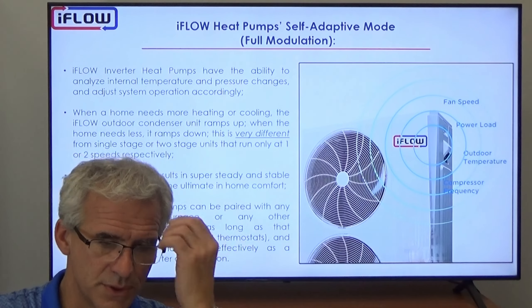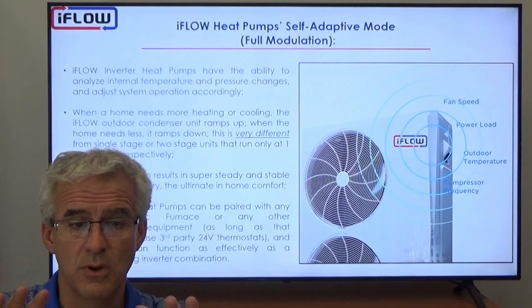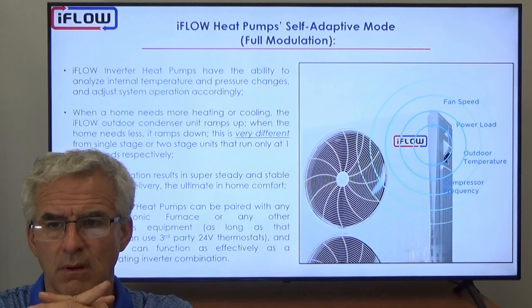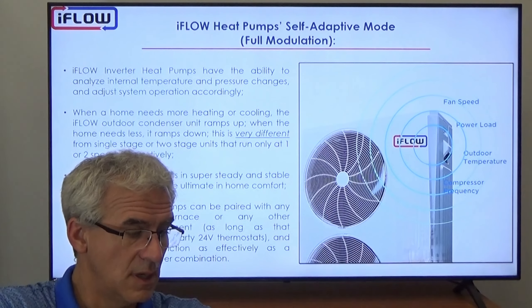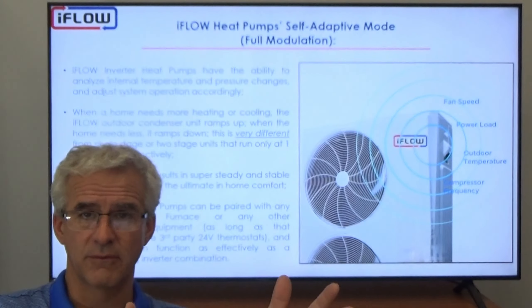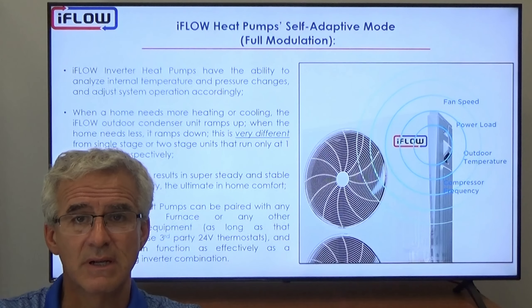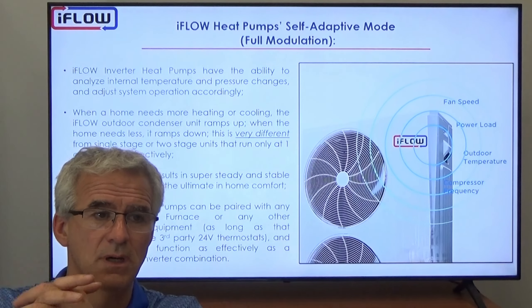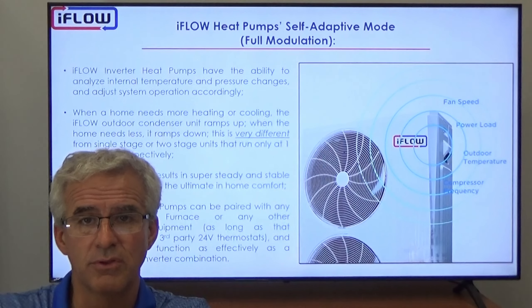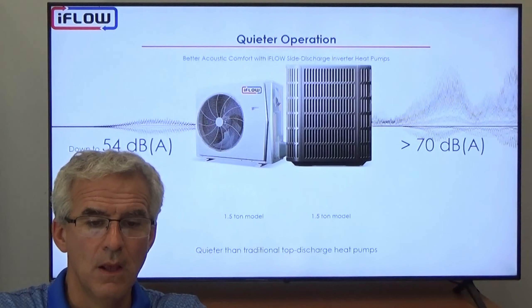Because of the self-adaptive capability, iFLOW inverter heat pumps can connect with any equipment — you can pair the iFLOW heat pumps with any other furnace and any other thermostat, as long as that furnace can accept a 24-volt third-party thermostat. That's the only criteria. If the unit can work with a third-party thermostat, we can connect to it and make a great system. Units are also very quiet — all side-discharge, running down to about 54 decibels, compared to traditional top-discharge cube units that run at greater than 70 decibels.